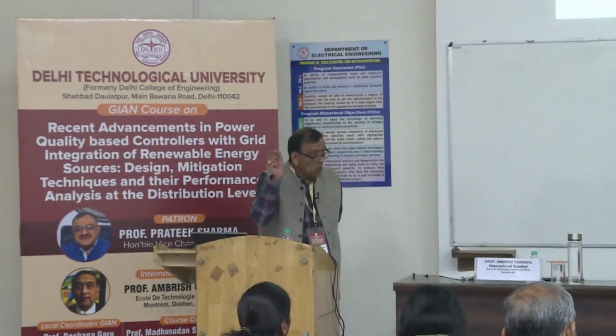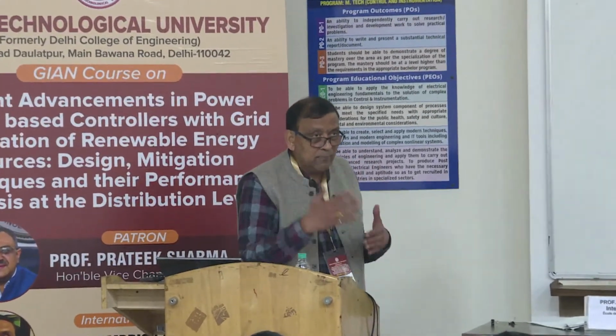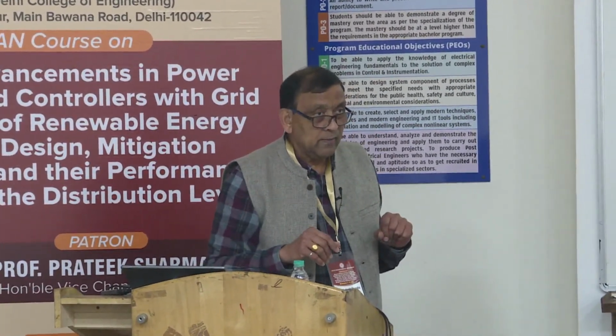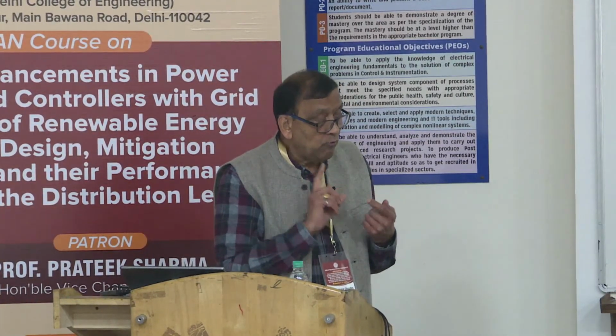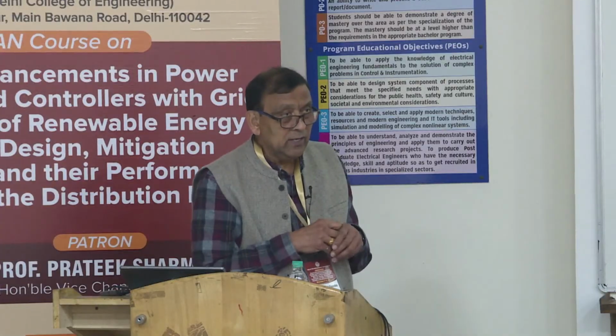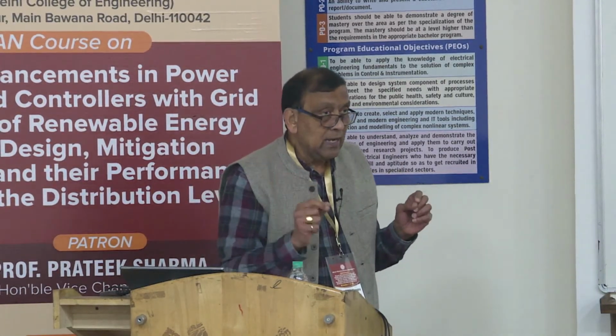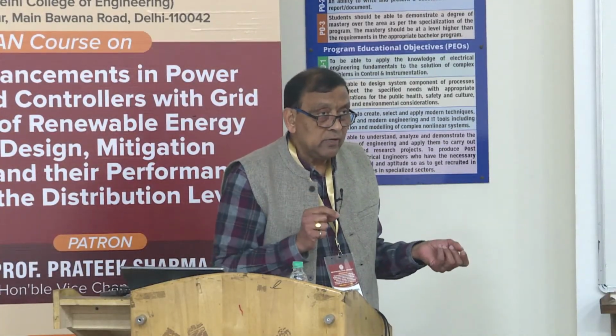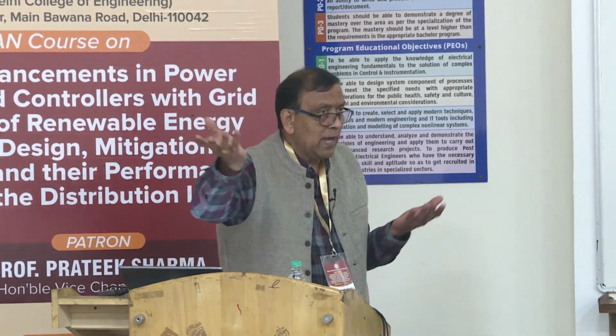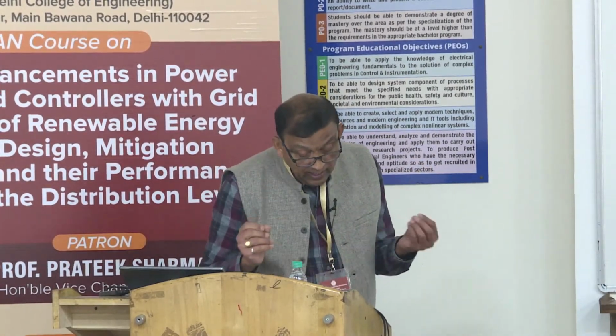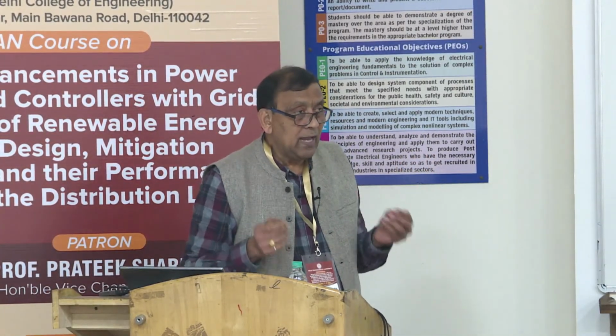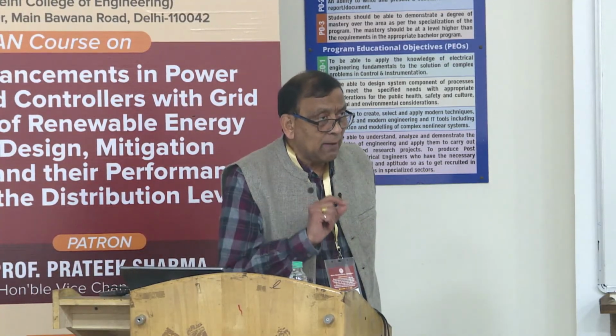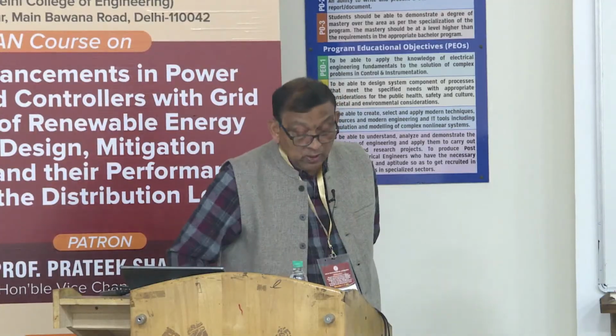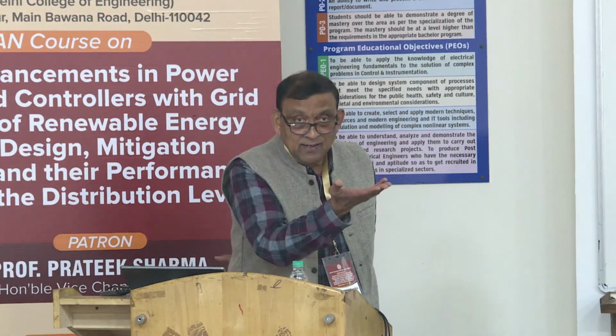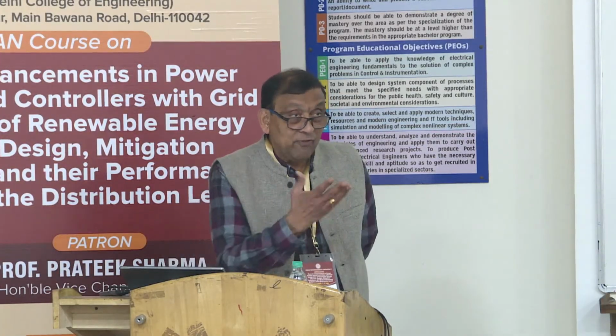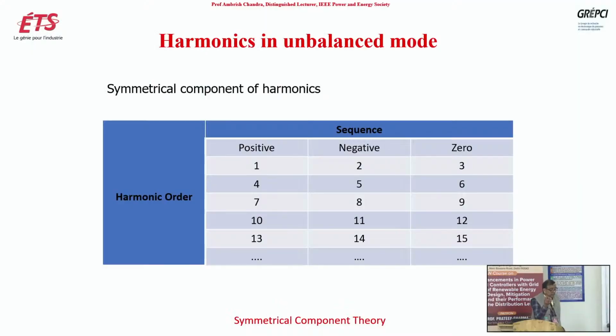So you don't have to do all those calculations. That is just to verify mathematically if you are right or not. So this is very important to find. Before you do the harmonic cancellation, you have to know if a certain harmonic is a positive sequence or negative sequence. Zero sequence you will know anyway, multiplied by 3 it will be easier. Okay, tell me the 29th harmonic. If the 29th harmonic is a balanced harmonic, what will be the sequence? Negative. See, so fast you can tell. It's a very easy thing. You just have to know the trick, right?